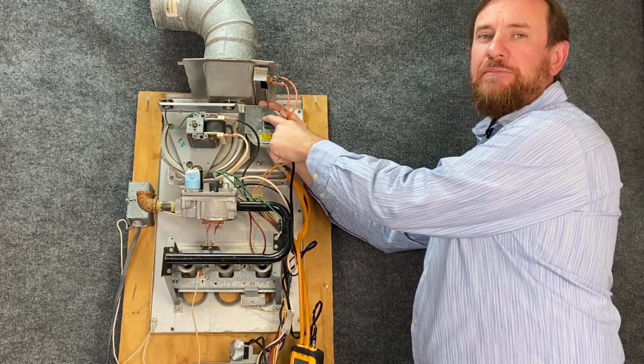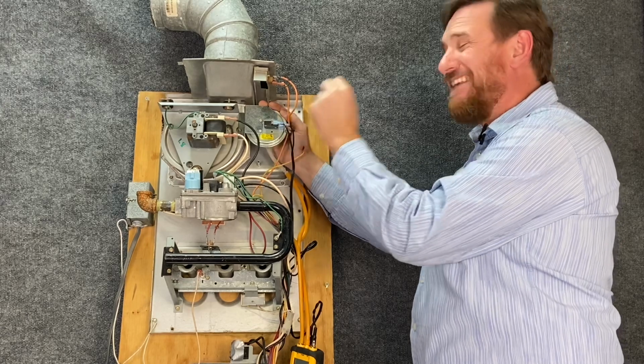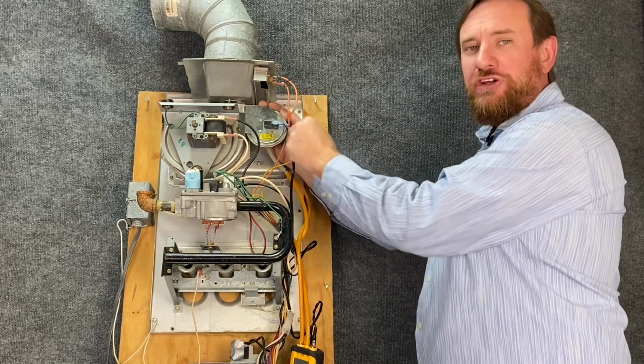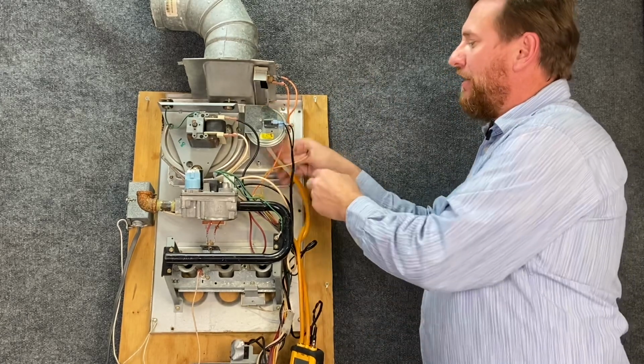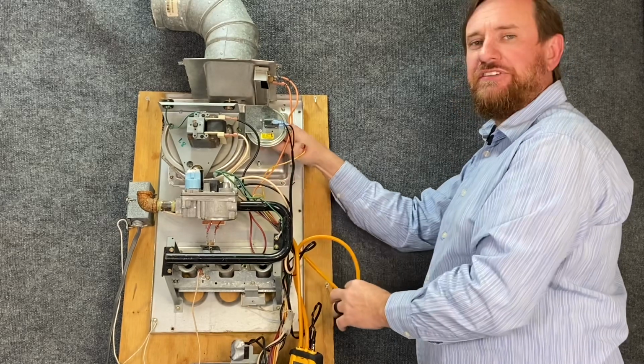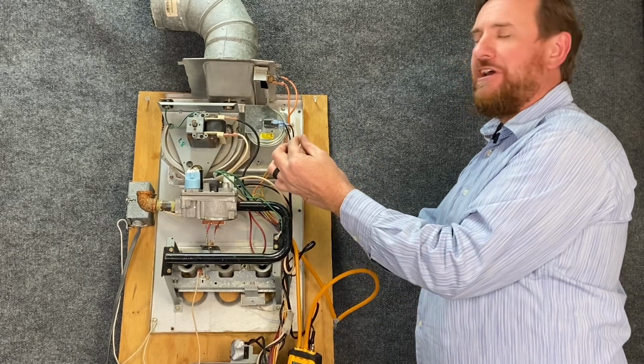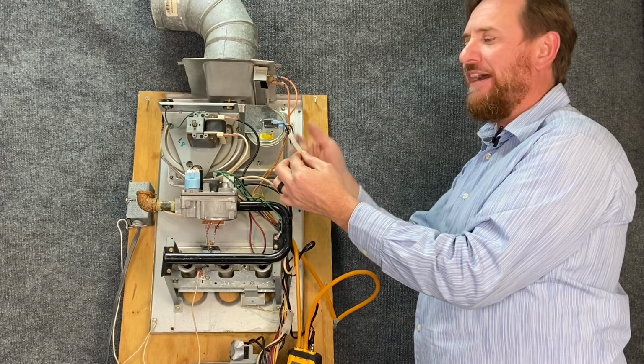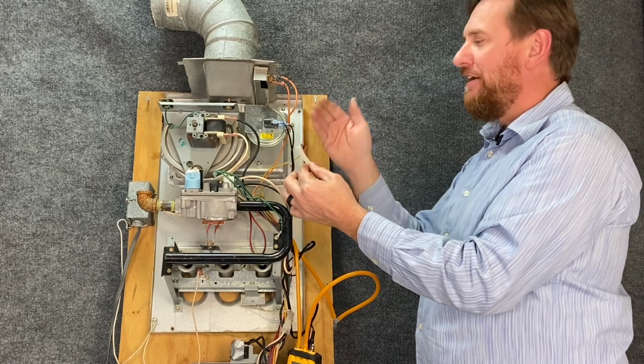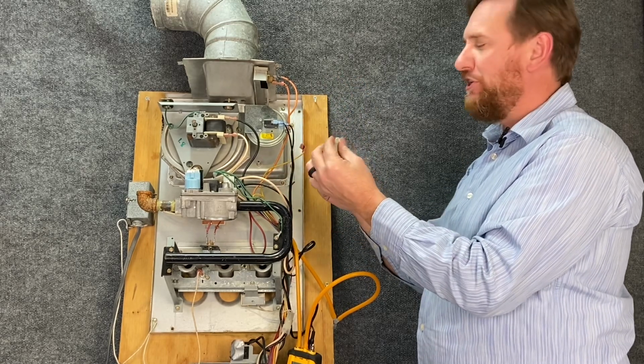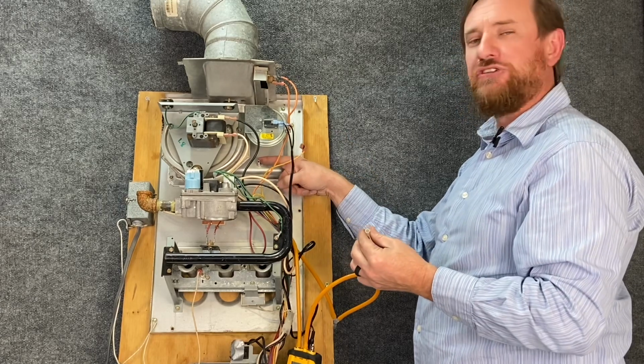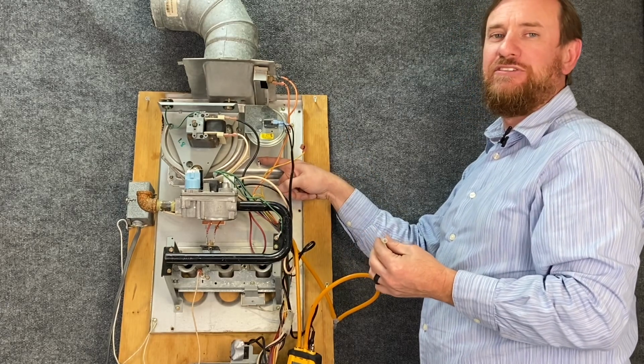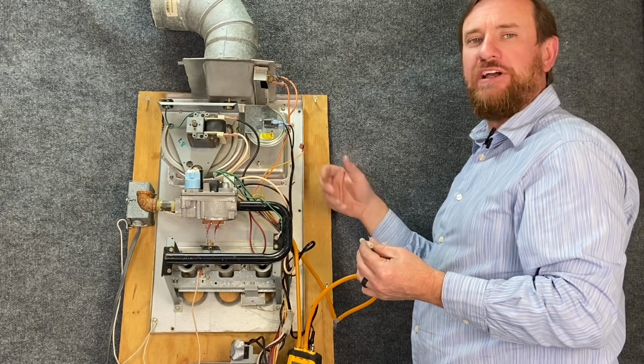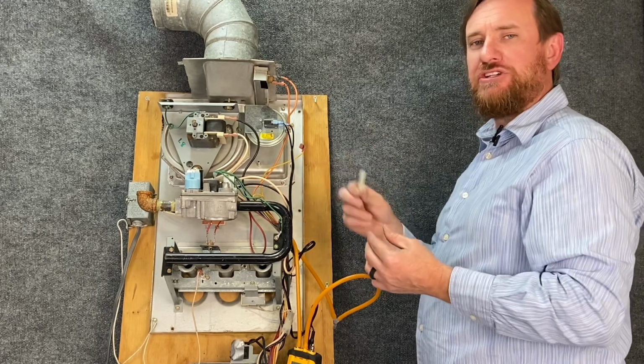This one closes at 0.25. I want to make sure without a doubt that my new one closes at 0.25. The other thing you want to check is these hoses. The hoses that connect it become brittle over time. They can be cracked, they can pull air in, and that air can make the switch not get a good seal. So you want to check this, and also sometimes this little tube where it connects into this inducer draft can clog up with rust or other contaminants. So you want to make sure that's in good shape.